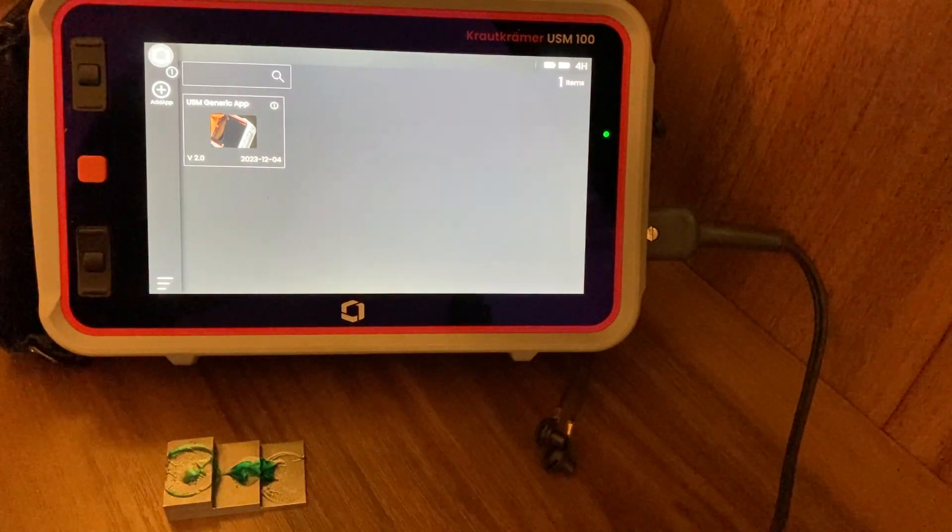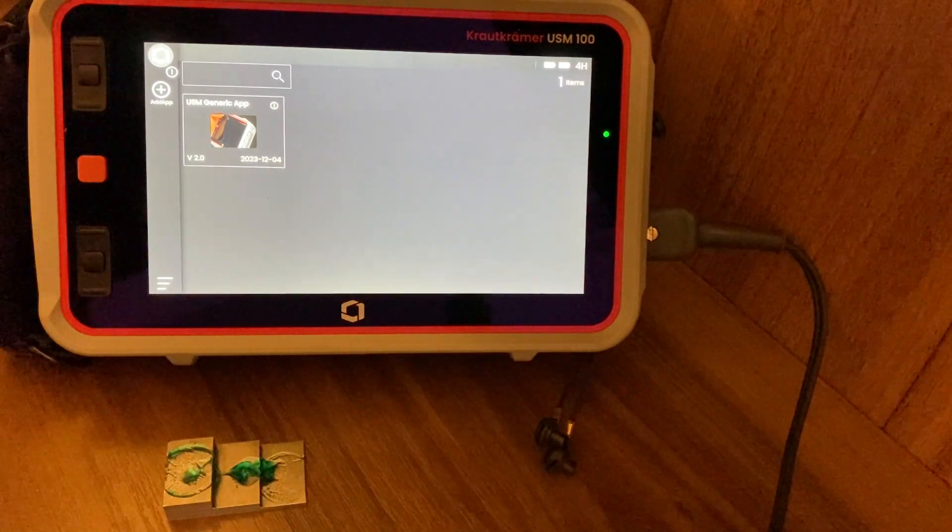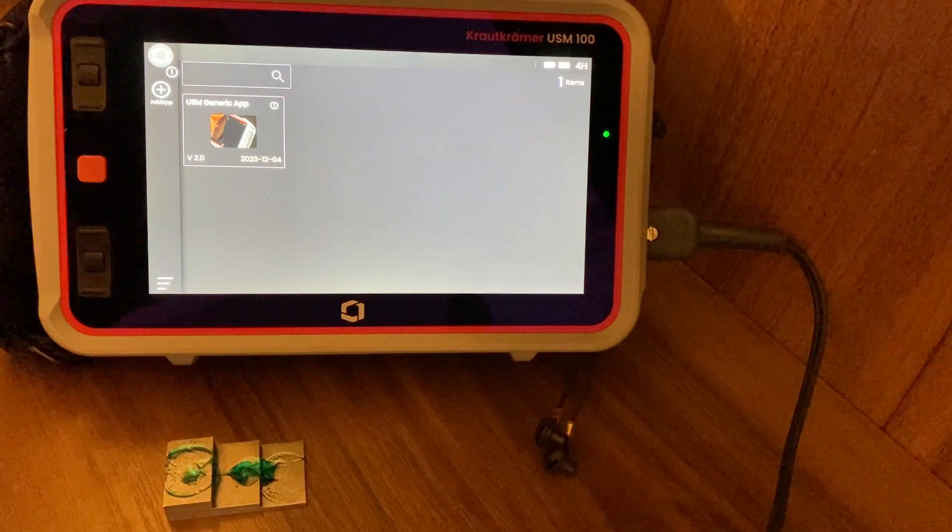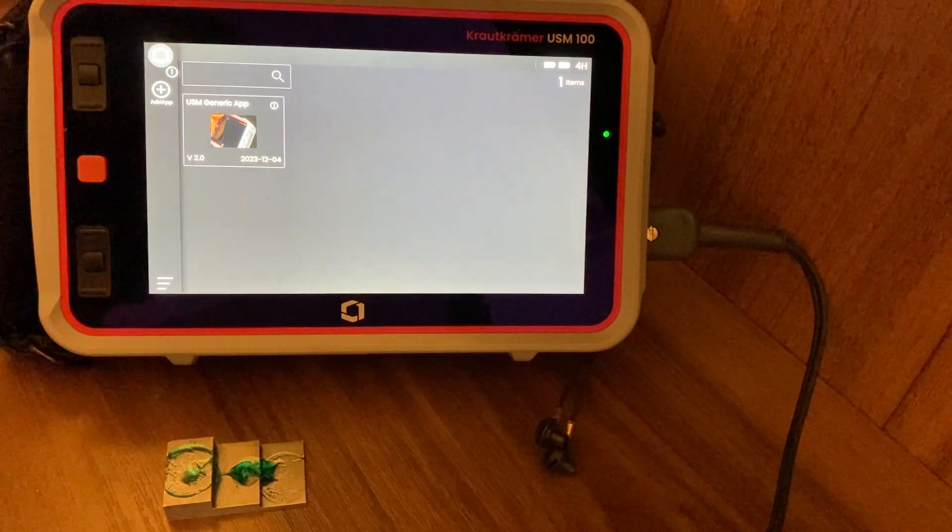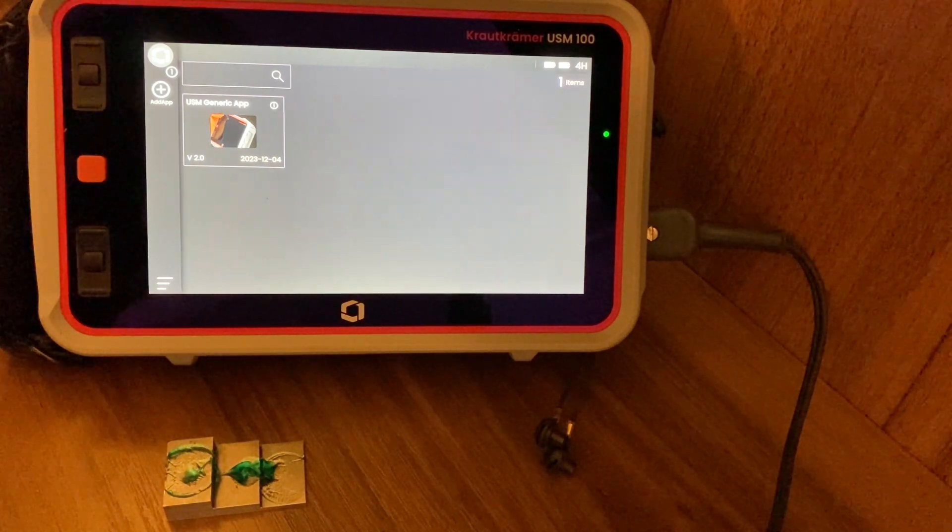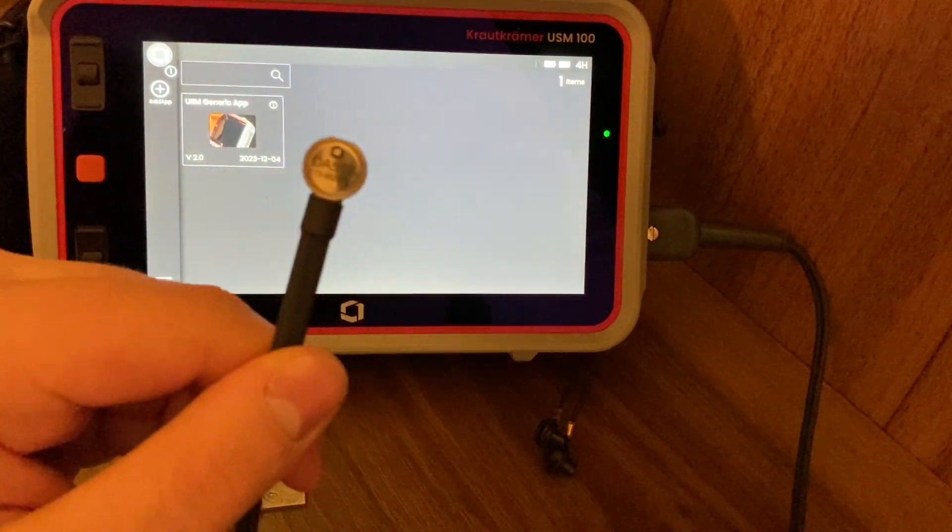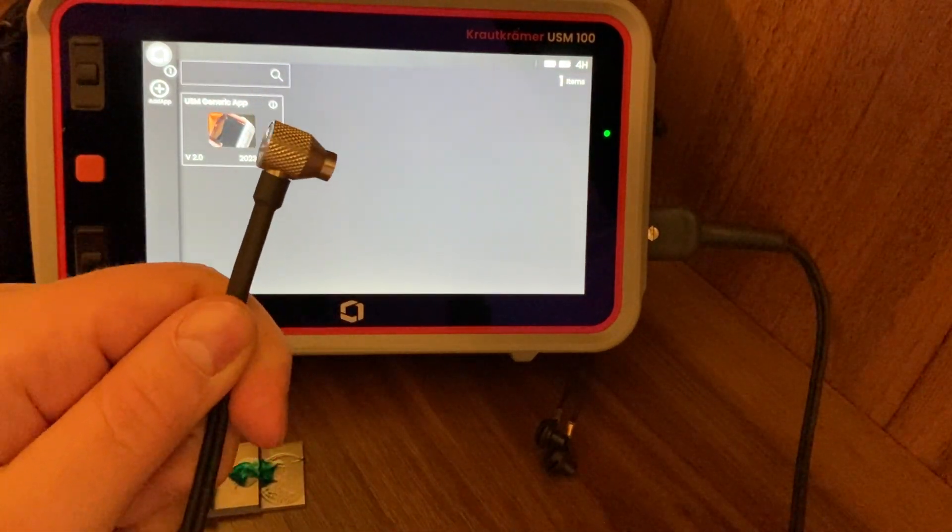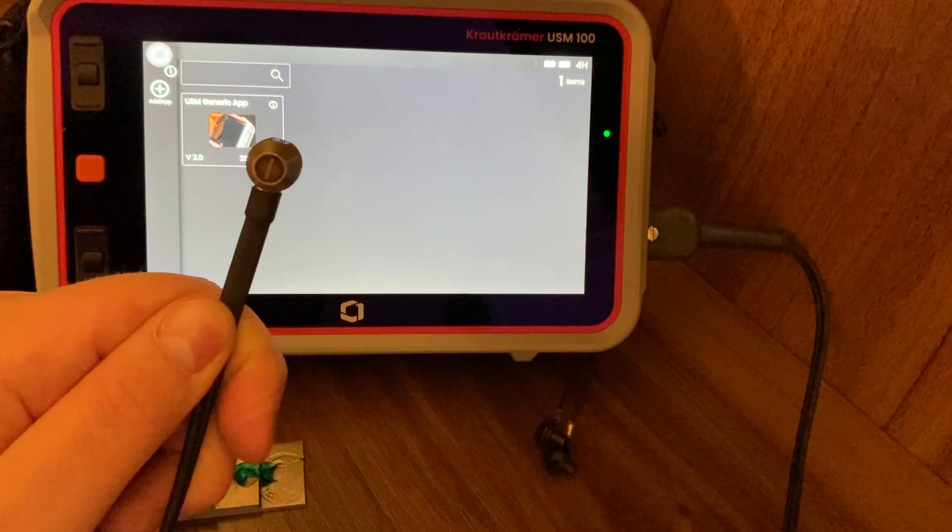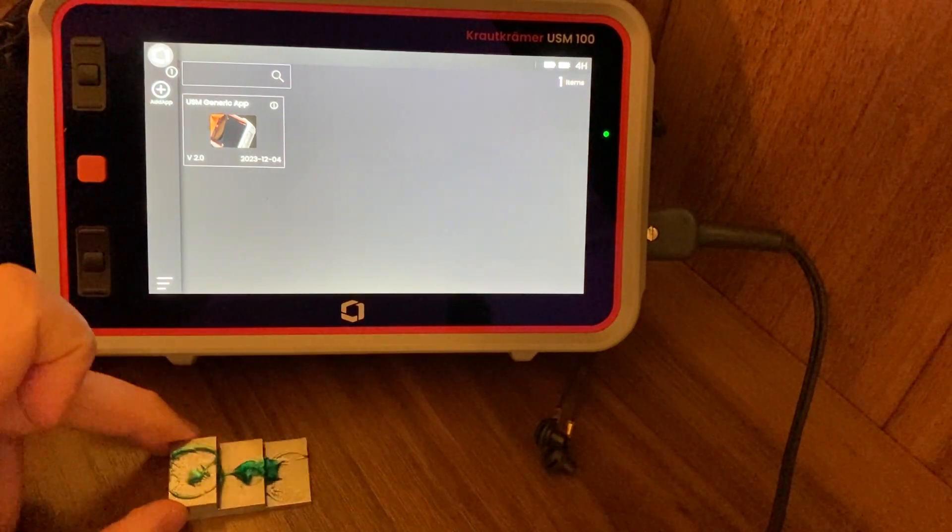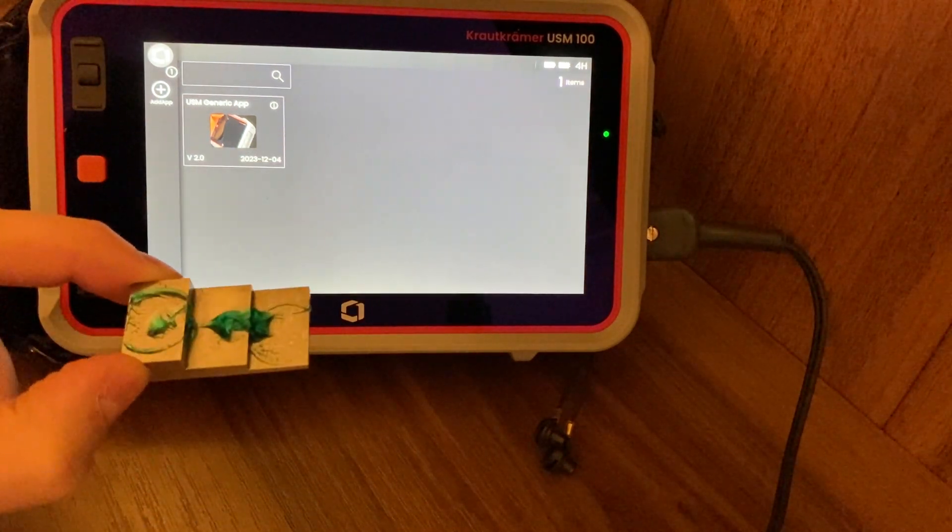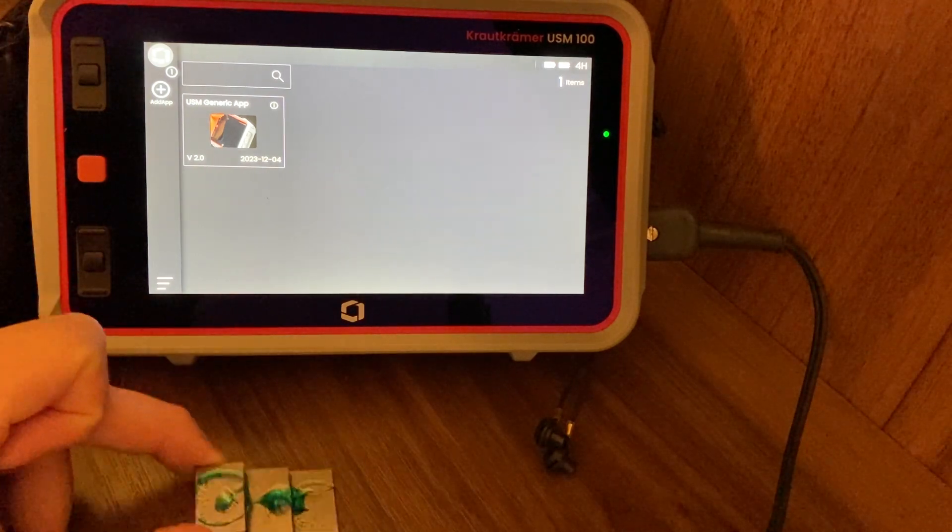Hi everyone, just a quick video to show you the Krautkrämer USM 100 by Wega Technologies and carrying out some standard routine thickness checks. Today we have a trusty little DA512 fingertip probe twin crystal. We have a step wedge step block here - 2 mil, 5 mil, and 10 mil.